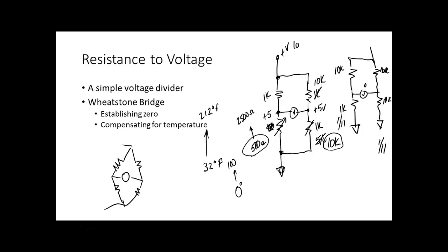Yeah. So your Wheatstone Bridge, you're going to have to balance it or set a reference. Now with scales, we do that outside with a load cell, which is a device that measures weight. We set 0 outside, so we go out there and we'll take all the weight, because even on a scale, you always have weight on the scale, right? Yeah, we call it the bridge. Truck scales, we call them bridges, or whatever sets that you put your stuff on. On a truck scale, we used to call it a bridge, because that's what it looked like. The trucks would drive up on the bridge.